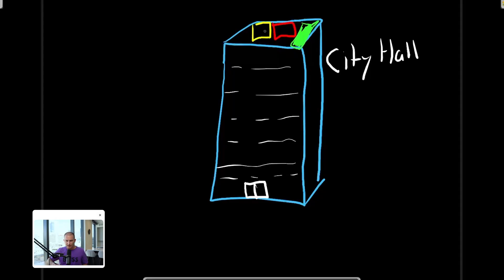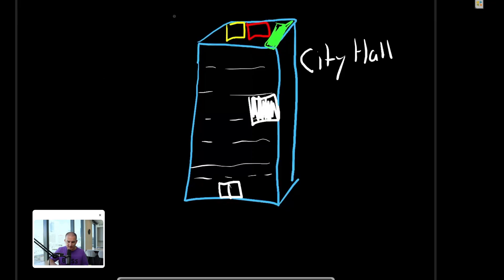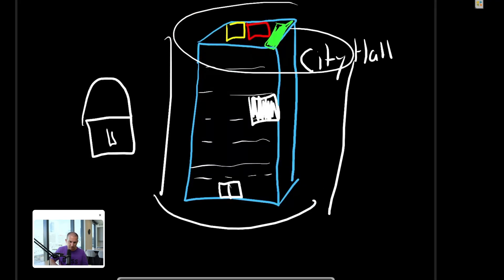Picture conference room five empties — sensors detect the vacancy, and the thermostat drops five degrees to save energy without sacrificing comfort. When the air filter's pressure climbs, the system triggers an alert to service it. A maintenance ticket auto-generates before performance drops. Energy savings dashboards update live; operators can see a 10 to 15% utility drop within weeks, sometimes more than 30%. This functionality typically would exist within a data silo — locked away and inaccessible. With a UNS, it becomes accessible.